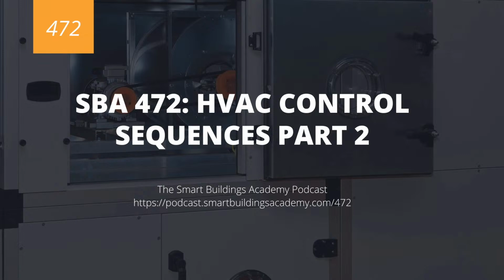All right, and we also tend to have a discharge air temp. Sometimes we will have some safeties in the form of static safeties, as well as low temperature safeties. There you have it. Those are all the points we have. So let's talk about the sequencing. Pretty much exactly the same as a fan coil, right? The fan might run all the time during occupied. It might only cycle on when we're in a heating or cooling mode.